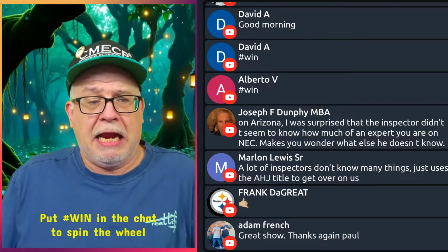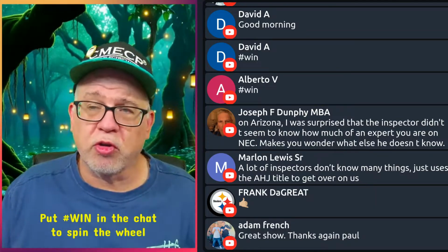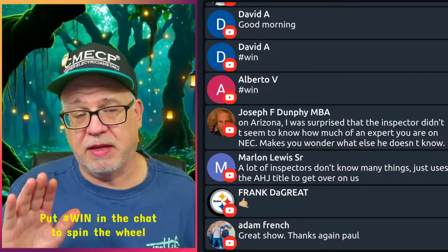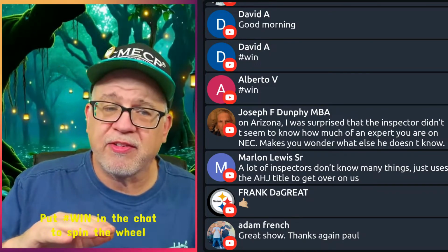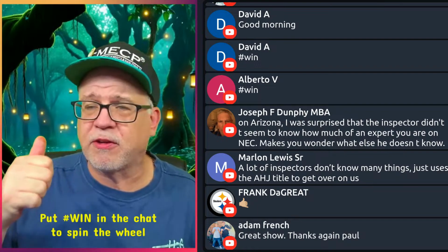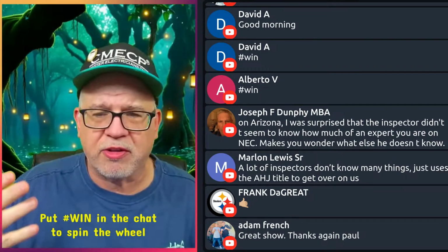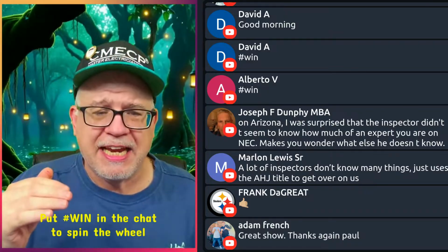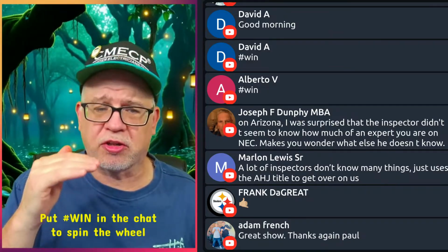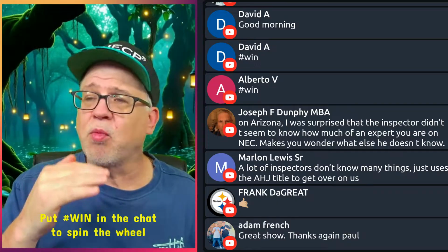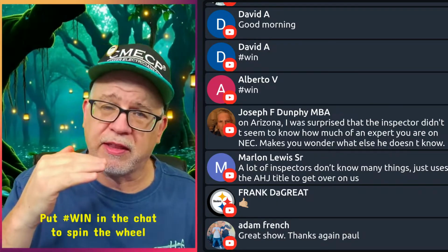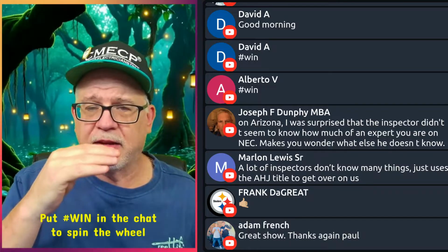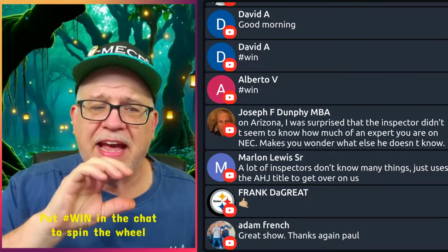Dude, relax. The small conductor rules in 240.4(D) have an allowance. There's another table here that says if you're dealing with HVAC, if you're dealing with motors, it gives you some other options. Look, relax. If you look at that nameplate, you'll see what the running current is, and you'll see that it is more than covered. Usually it covers not only the air conditioning compressor, but also the fan motor, the condensing fan. So you'll have that value.